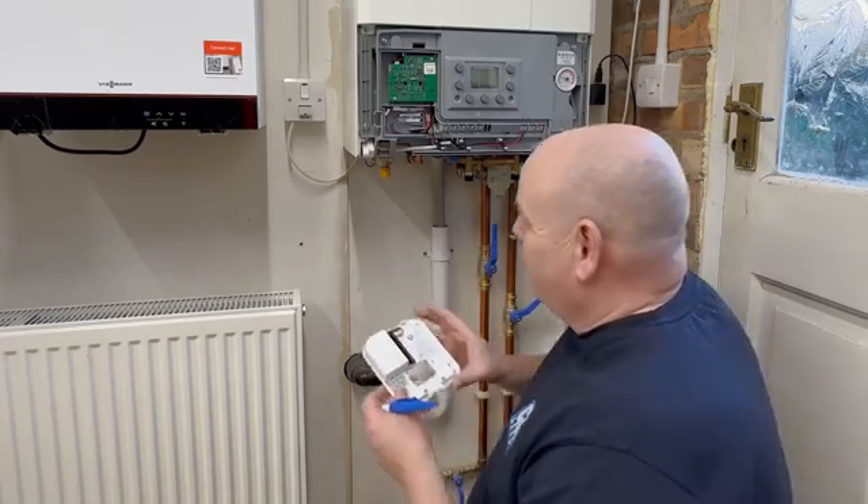The BCM is now totally wired up. We've got live, neutral and earth in there. The T1 and T2 connections go back to the receiver for the thermostat, and B1 and B2 go to the OpenTherm connections on the boiler. You'd need to check your own installation instructions for that, and if you have any questions give Vericon a call.